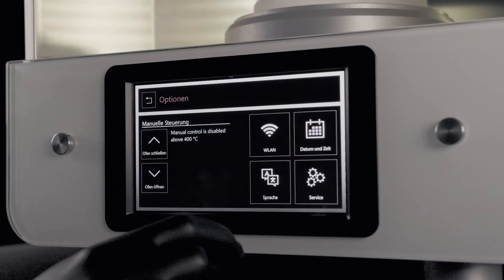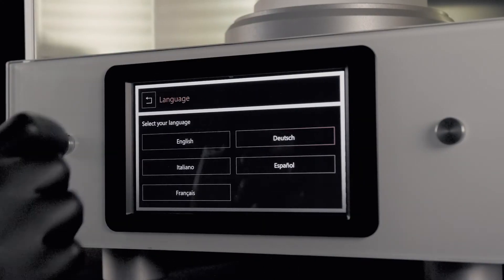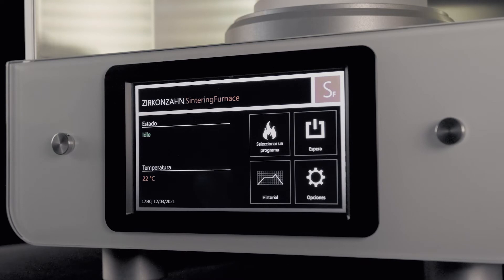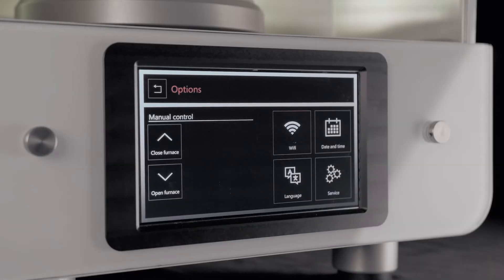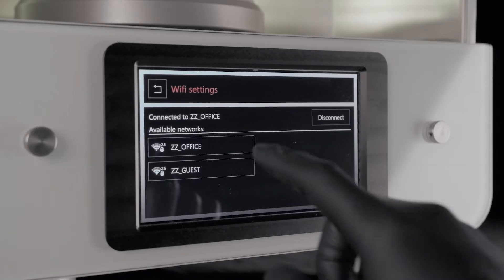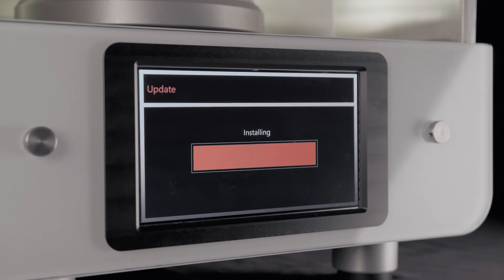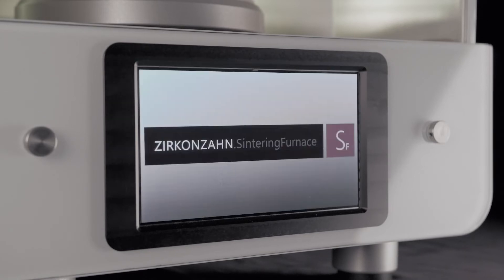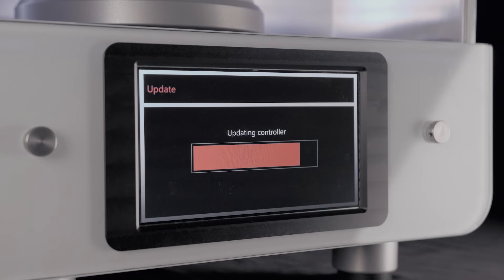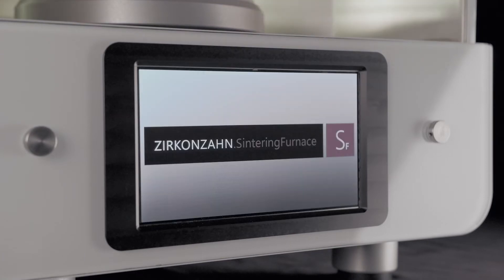The software is now available in additional languages. A good internet connection helps you download and install updates directly on the furnace. This has several advantages: the latest software updates and sintering programs are always available, and it is no longer necessary to contact technical support to install updates, saving a lot of time.